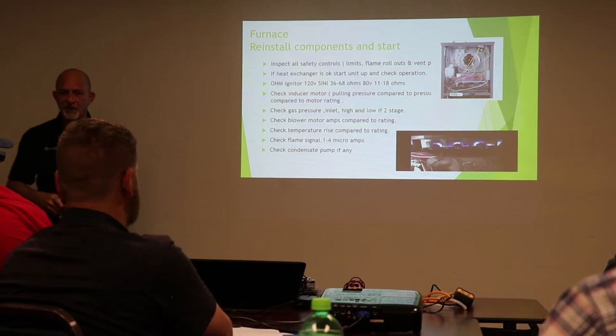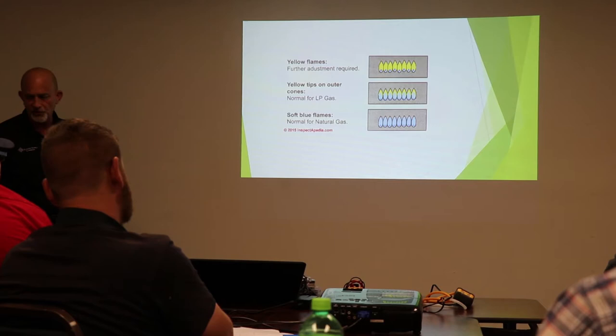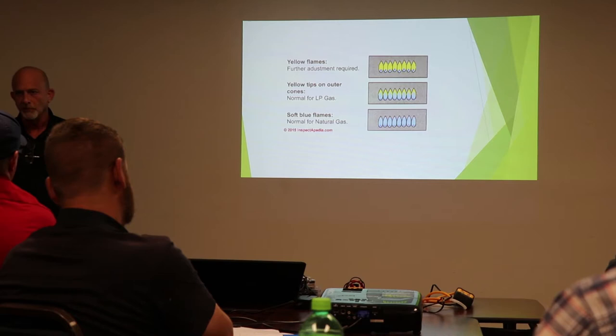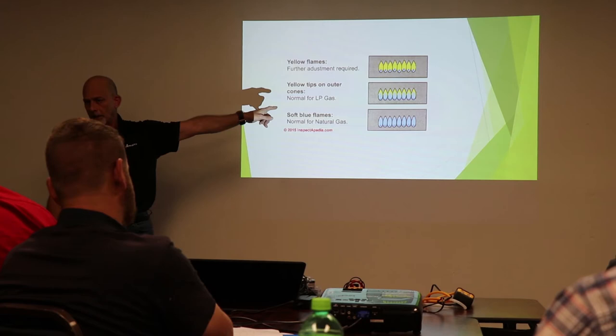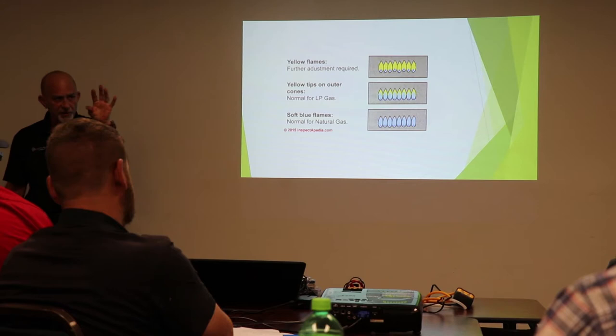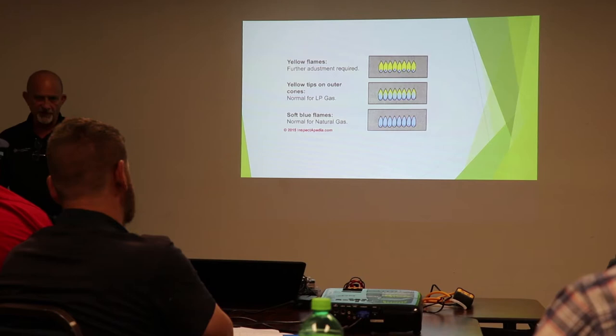Looking at your flame when it's burning, more so on an old ribbon style, you can see them better. If you got yellow, not good. You gotta adjust your air curtain. You could have yellow tips on LP though. That is normal. Natural gas better be blue. Anybody see orange speckles in there? Don't worry about orange. That's dirt. As long as the flame's not completely orange, but if it's burning, you'll see orange here and there. That's just dirt being sucked in through the flame.